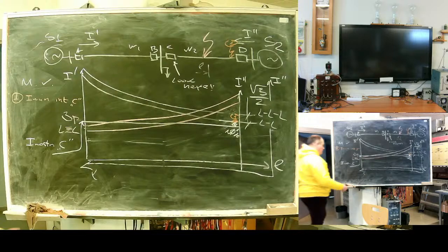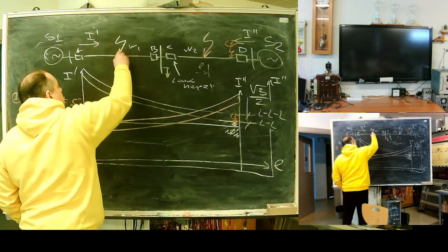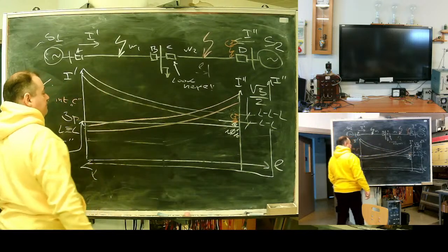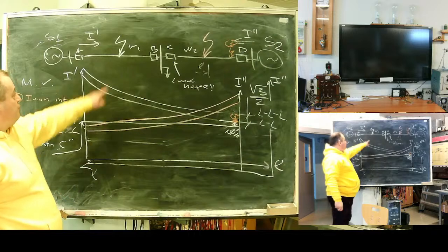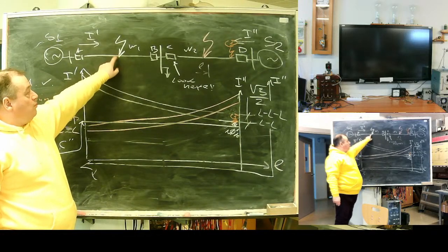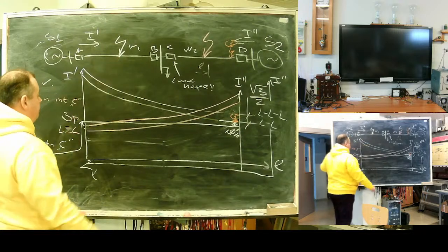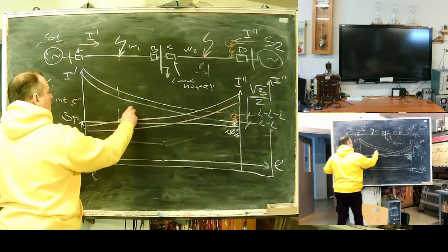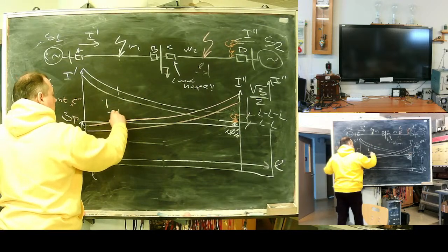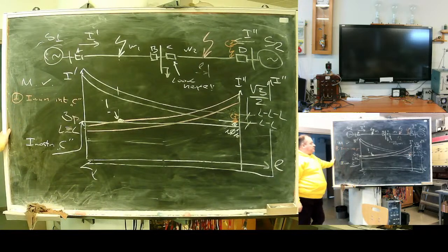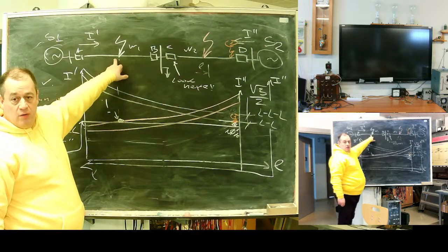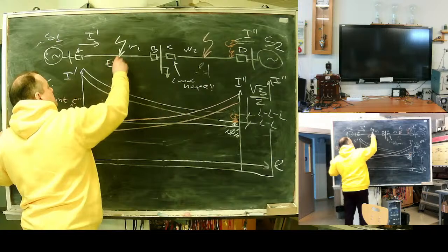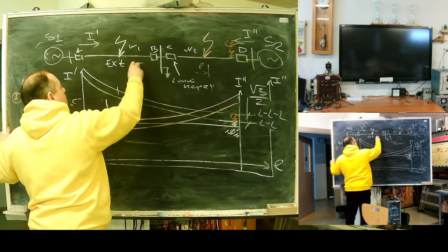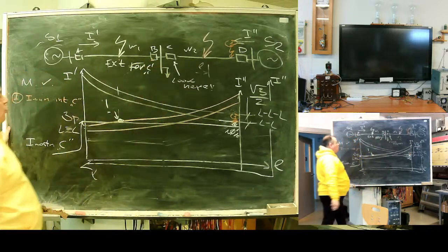But I can create this fault. What will be the current for this fault through my protection C? I think this one. Yeah. And what will happen? My protection will operate falsely. Is this fault internal? No. This is an external fault for C. So my protection should not operate.